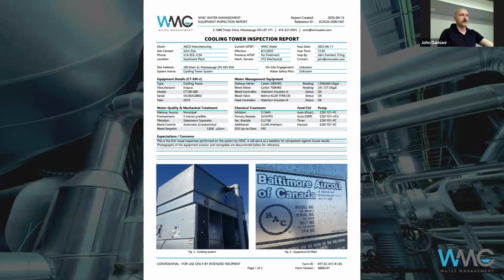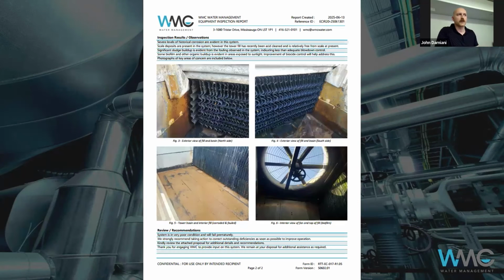This is what it might look like when you have problems in the system. You've got active corrosion, historical issues. This system had experienced several failures before we took over the water treatment program. They had tried to recoat a lot of the galvanized with new zinc coatings, but those had stripped back off. You can see the basin is corroded.